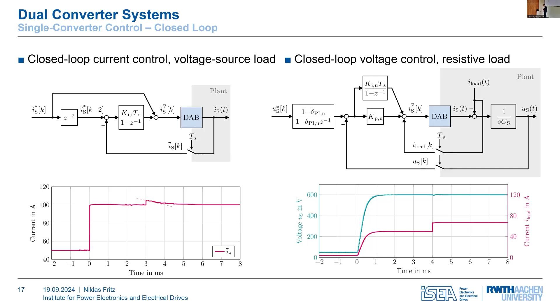Because you usually don't have a high power source or a high power load, what you do is run the power in a circle. In this case, only the source has to deliver the losses to the system. In such a setting, you have two control goals: first, you want to control the voltage on the open secondary side, and second, you want to control this circulating current.